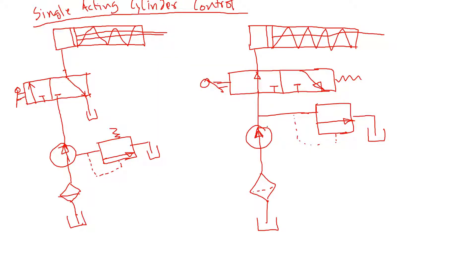Single-acting cylinder control: a single-acting cylinder can only extend — it moves in one direction. So if the fluid is coming this way, it will extend all the way and then stop. There is no back and forth. That's called a single-acting cylinder. Now this piece here is a directional valve — it basically directs the flow.